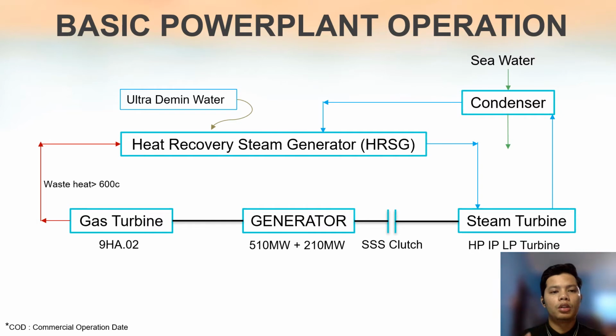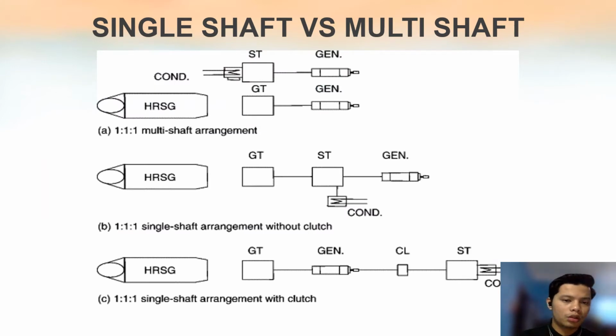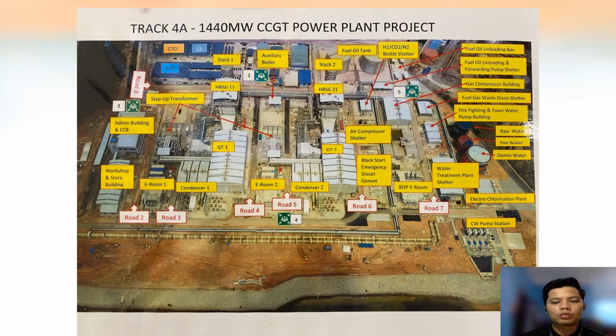At this stage, the gas turbine and the steam turbine must be connected in order to generate the 720 megawatt of electricity. It will be connected by triple S clutch to be a single shaft arrangement. The used steam will be condensed by the condenser to be heated by the HRSG to produce a steam. So this is the difference between single shaft arrangement with the multi-shaft arrangement. For this power plant, it will be used the single shaft arrangement with clutch. So this is the overall layout for this power plant.